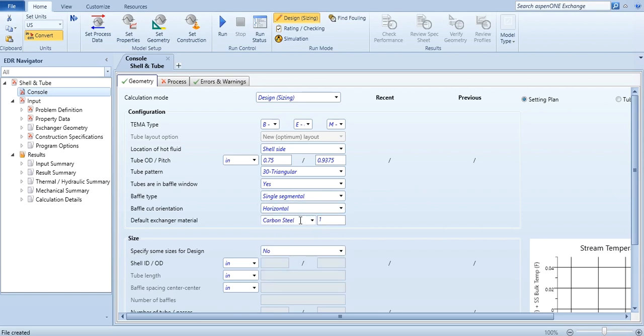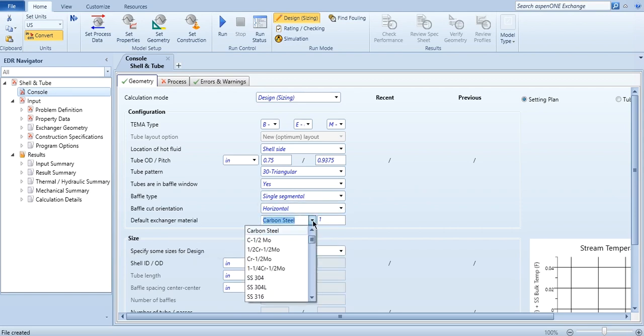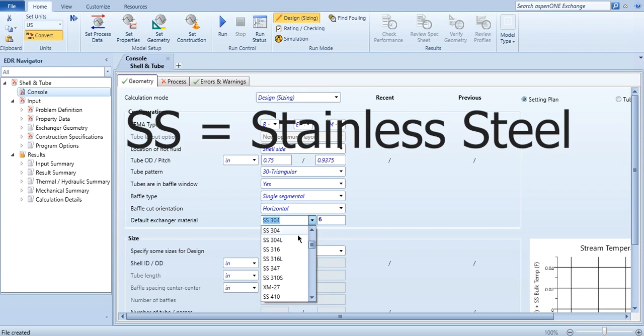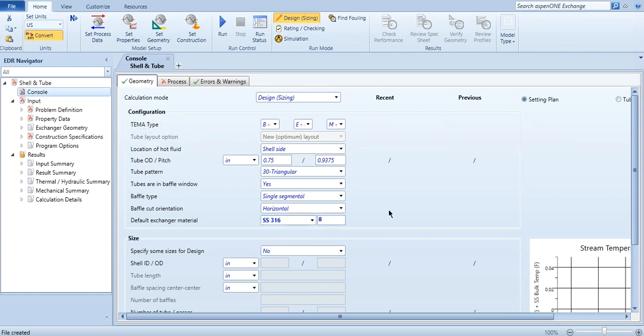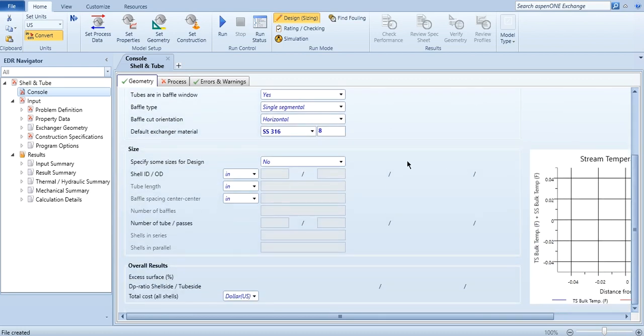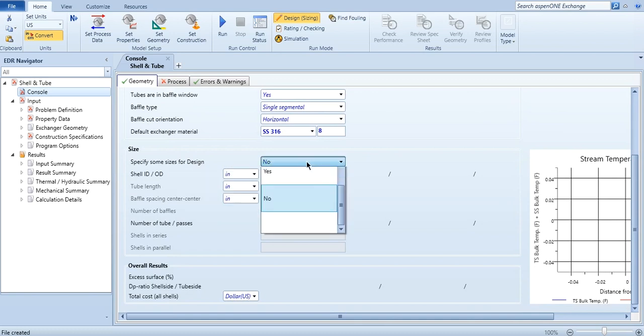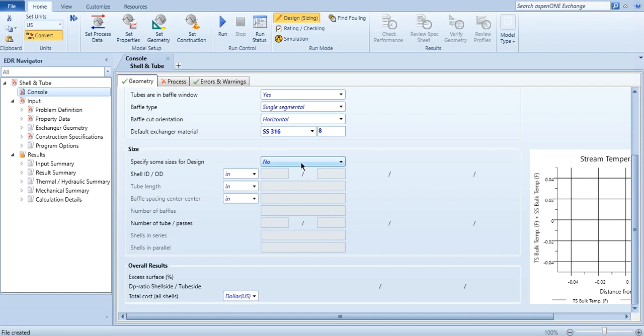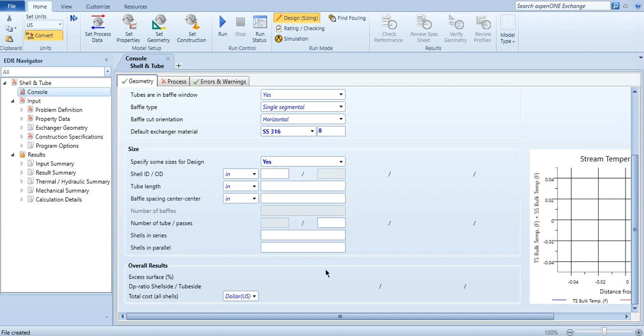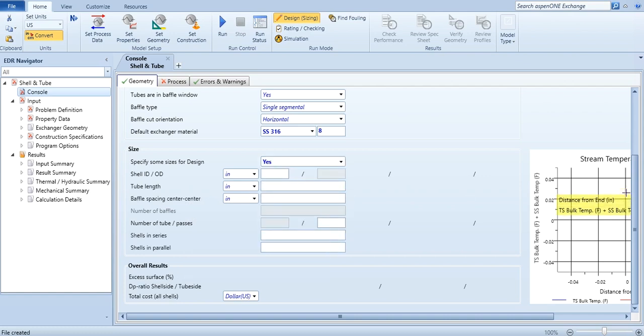And again you can even select the heat exchanger material - for carbon steel it is 1, for SS304 it will be 6, similarly for SS316 it will be 8. So it will also have some impact on heat exchanger design. And similarly, if you want to rate it as well, then specify some designs for sizes for design. If you click no, it will not open. If you click yes, it will open and you can give the design information over here as well.